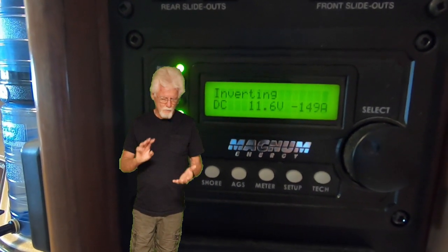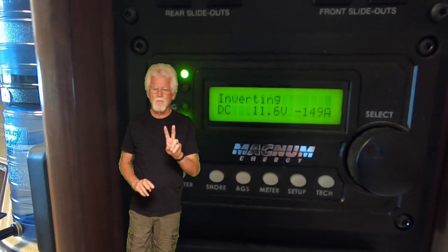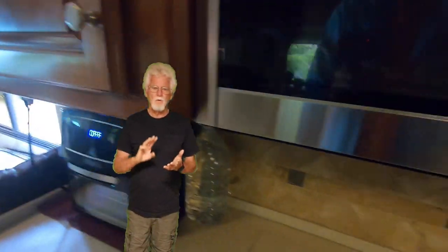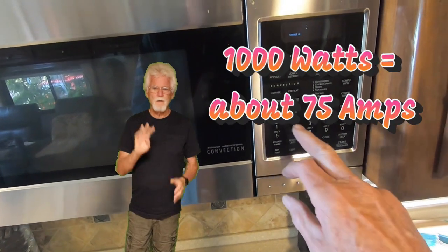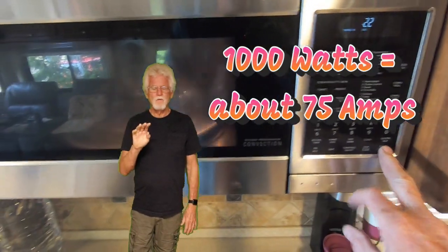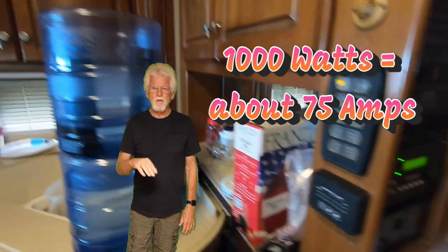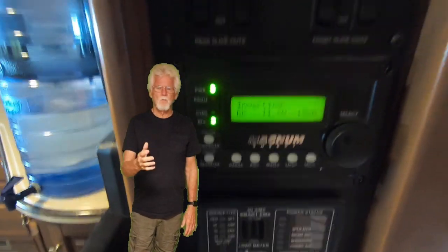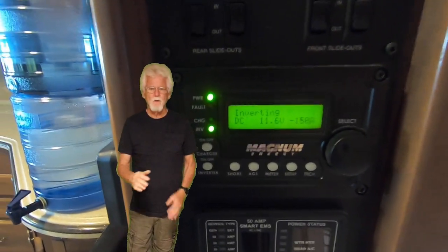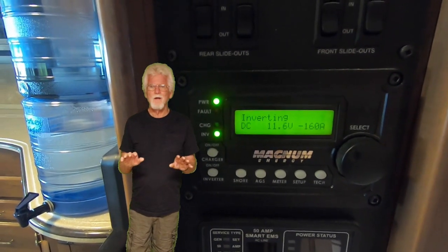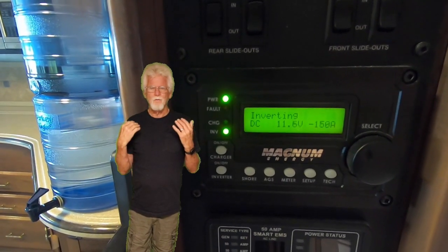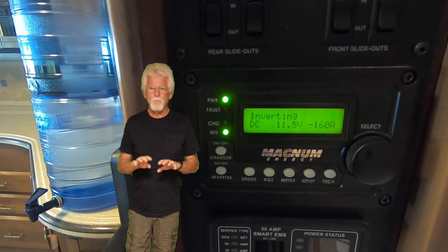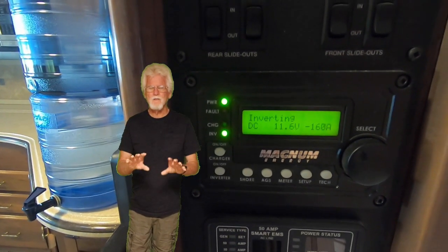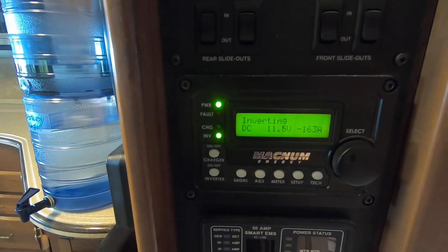I think what we'll do next is connect another battery — run 2 batteries and see how it does. I did look it up in the Magnum inverter manual, and it said to run a load over 1,000 watts you need at least 400 amps of batteries, so we're not giving the inverter near what it wants. But that's okay, because we're trying to test the batteries, not run the inverter. We want to push them as hard as we can and see just what they're made of.